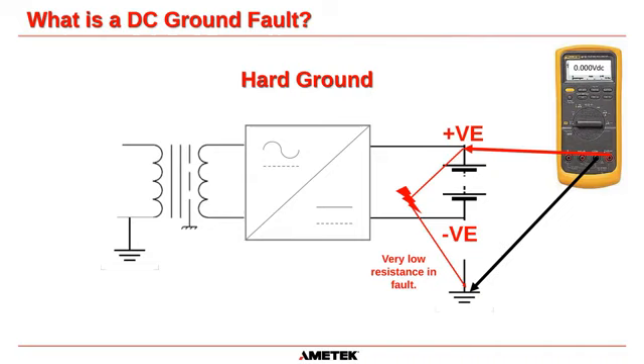Okay. Now, there are two terms that I hear a lot: a hard ground and a soft ground. A hard ground is when that connection to ground is very low resistance. The fault has very minimal resistance. It's like a dead short from positive to ground. So if you took your Fluke and measured between positive and ground, you should see 0 volts, because there is no potential anymore between positive and ground. They're at the same point.